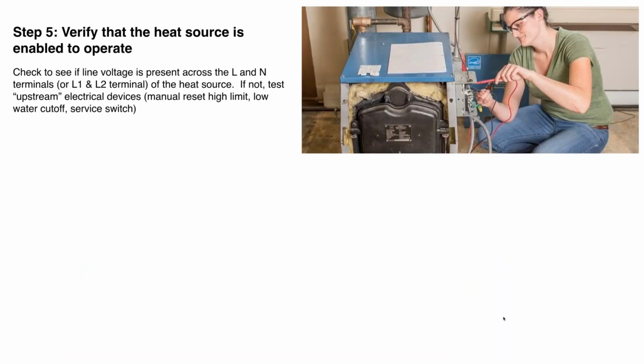Okay, verify that the heat source is enabled to operate. First of all, do we have line voltage at the heat source? If it's a heat pump, you're looking for typically 240 volts, 230 volts between L1 and L2. If it's a boiler, usually it's going to be a 120 volt circuit, line and neutral. Check it with your meter. Don't assume because the circuit breaker is closed that you've got it.